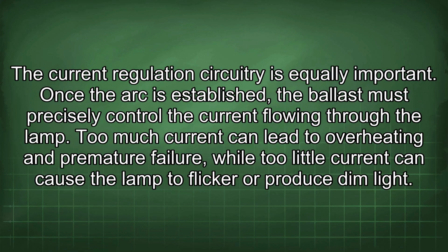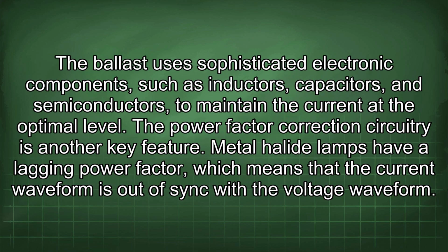The current regulation circuitry is equally important. Once the arc is established, the ballast must precisely control the current flowing through the lamp. Too much current can lead to overheating and premature failure, while too little current can cause the lamp to flicker or produce dim light. The ballast uses sophisticated electronic components such as inductors, capacitors, and semiconductors to maintain the current at the optimal level. The power factor correction circuitry is another key feature.